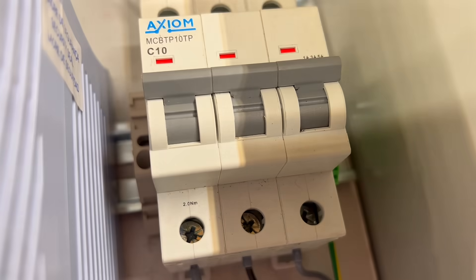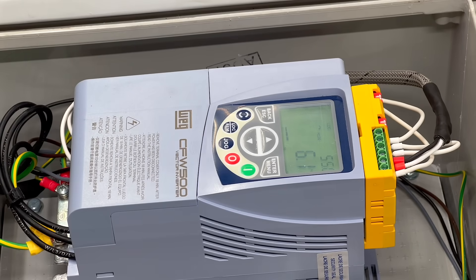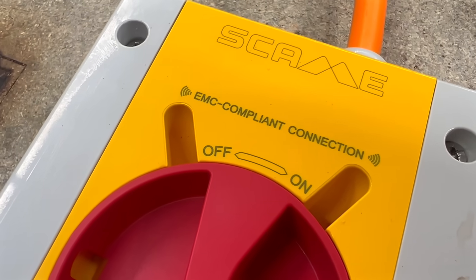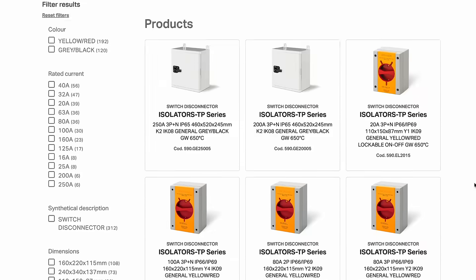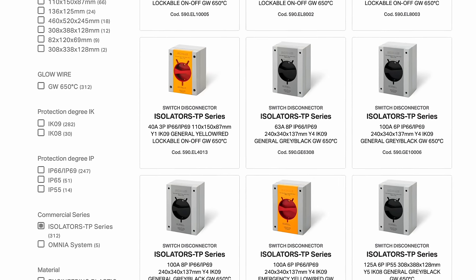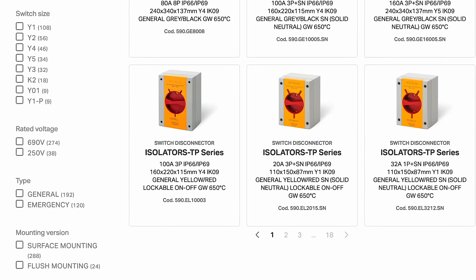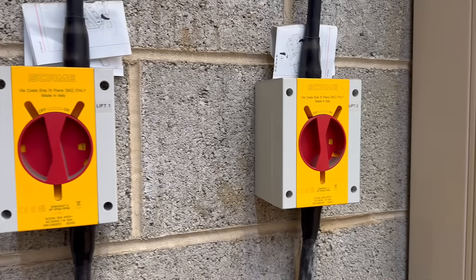Once the isolator is closed again, I recycle the power and can restart the motor. It's these two features — the auxiliary contacts for enabling Safe Torque Off, and the ease of connecting screened motor cables — that Scame uses to define this as an EMC-compliant isolator. It's part of the TP series, one of the most widely used isolator ranges out there, available in current ratings from 16 to 160 amps and in both emergency and general-use versions. I see these installed everywhere, from railways to air conditioning units.